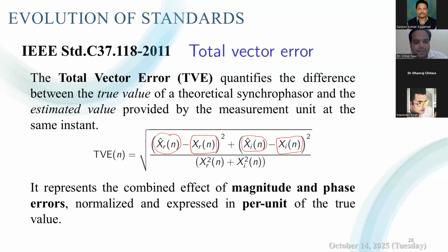So TVE, here you can observe this is normalized also. But sometimes we may observe that they have calculated the total vector error in terms of percentage. So for that purpose, they multiply it by 100. So we can say this total vector error is actually the benchmark for determining whether a PMU is good enough for accurate synchrophasor reporting or measurement or not.